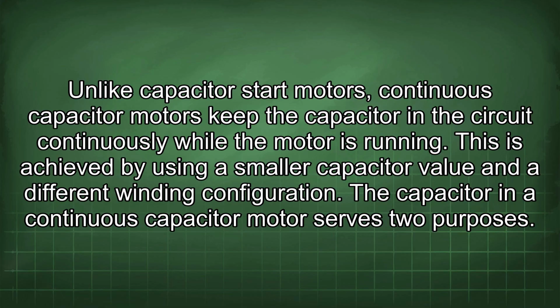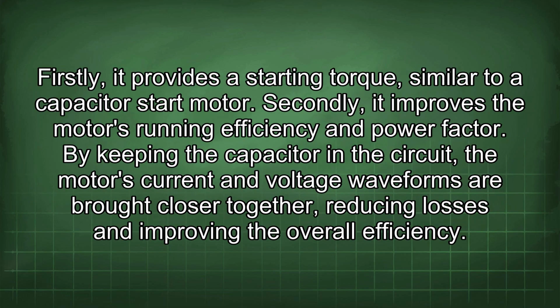This is achieved by using a smaller capacitor value and a different winding configuration. The capacitor in a continuous capacitor motor serves two purposes. Firstly, it provides a starting torque similar to a capacitor start motor. Secondly, it improves the motor's running efficiency and power factor.